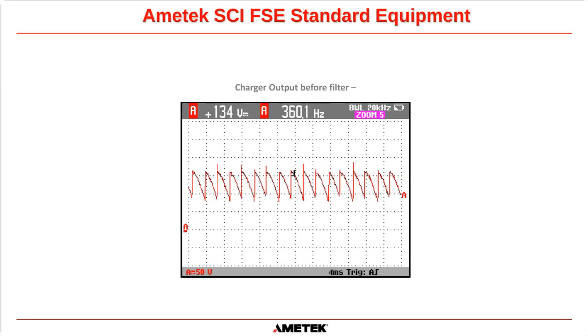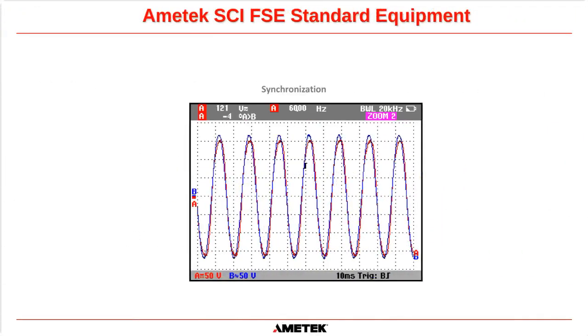So they do get shaken around a little bit when they're going on ground transport, and loose connections can be exposed. So an oscilloscope is a very good way to see that. We can also see a very good picture of the synchronization between the bypass and the inverter. It's difficult to see here, but there's actually 2 waveforms there. The red one is a little bit lower in voltage, that's the inverter, and this blue one here, that's the bypass voltage. And we can see that there is only -4 electrical degrees between A and B, and that's completely okay. We can say that that is a very good synchronized signal.